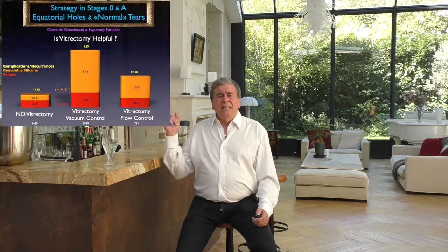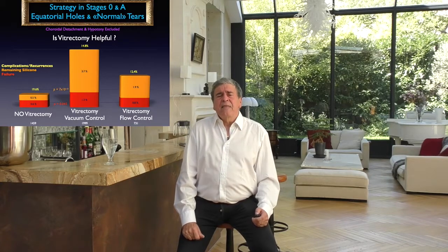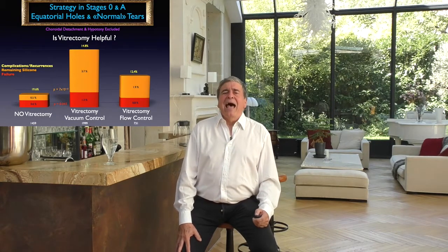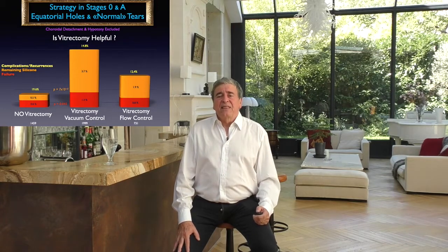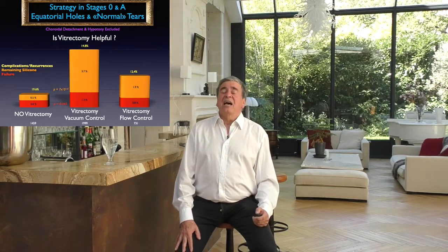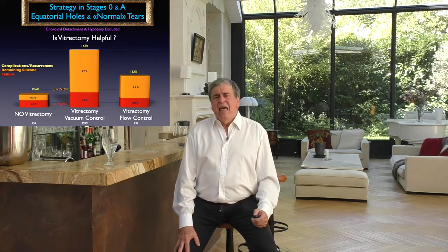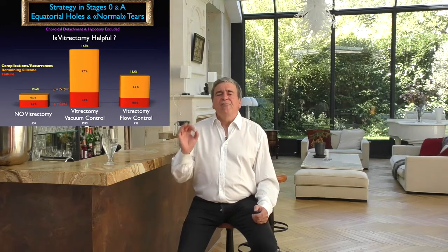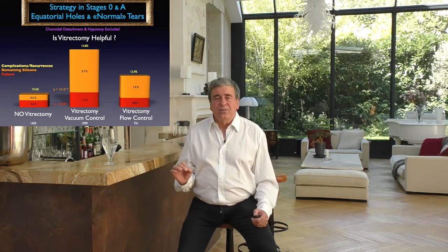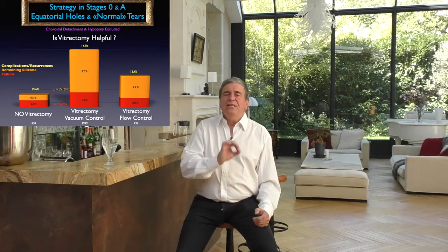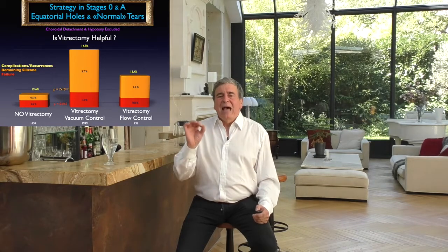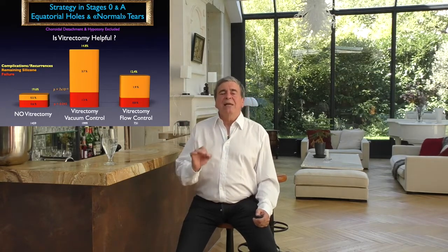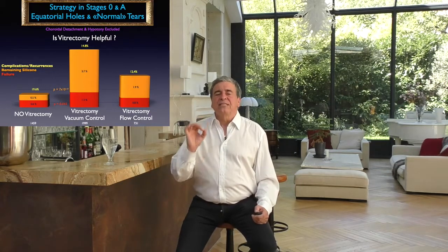Another interesting thing in the EVRE statistic is that detachments treated with a vitrectomy machine equipped with a Venturi pump have more failures than if they are treated with an aspiration flow control machine. This clearly demonstrates that the aspiration flow control has an influence on the anatomical results. Depending on the type of fluid control you have, you will have to opt for cutting and aspiration parameters that will ultimately not lead to the same result.